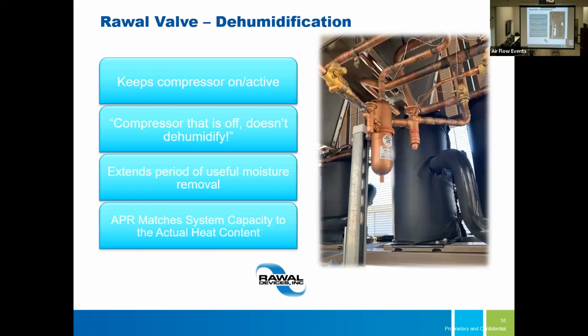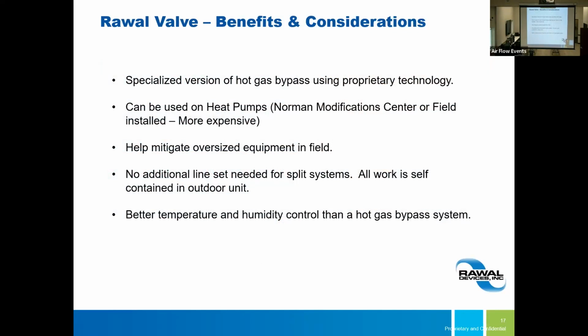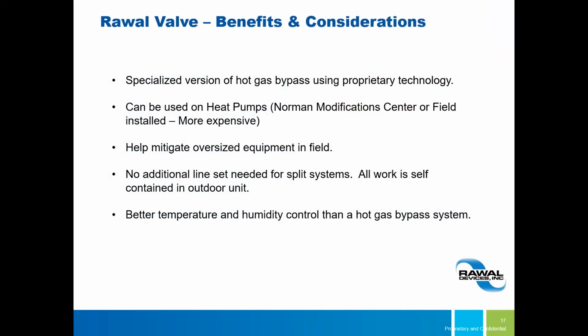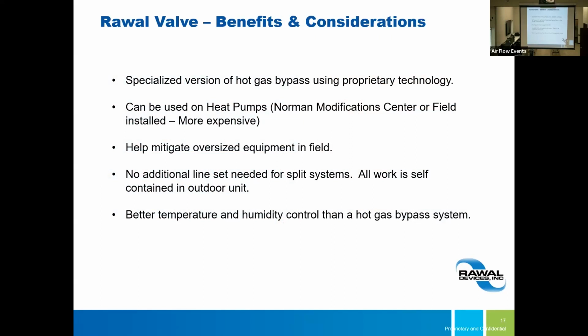I'm assuming you'd also sacrifice some comfort temperature with that, because you're essentially running the system longer, based on the humidity versus the temperature. So you'll satisfy room temperature before you satisfy humidity. Potentially, yes, that could come up depending on your circumstances. But again, it's going to modulate down low enough that you're not going to drastically overcool. So your discharge temperature won't drop drastically; it'll just creep down.